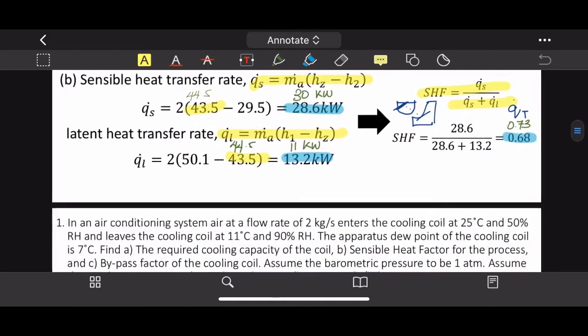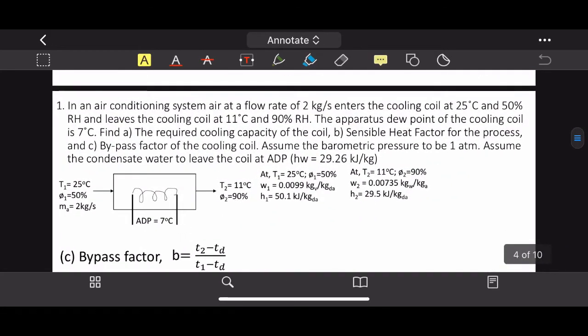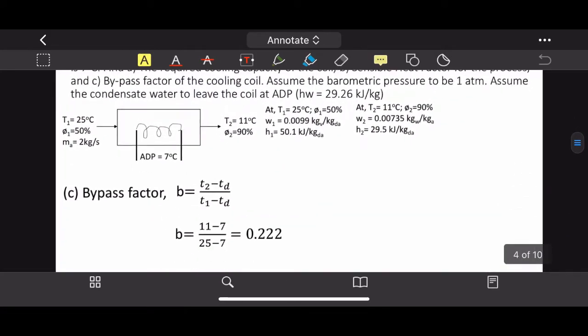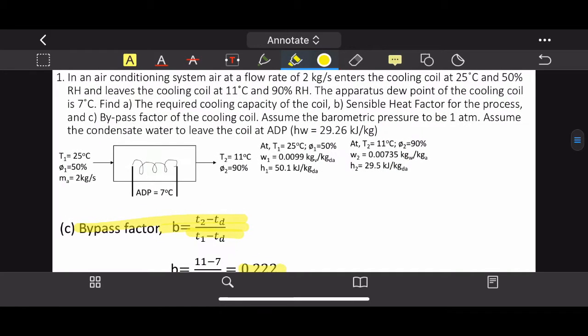Part (c), bypass factor, is straightforward. Using the bypass factor equation with t1, t2, and the apparatus dew point at 7°C, the answer is BF = 0.222. That completes Question 1.